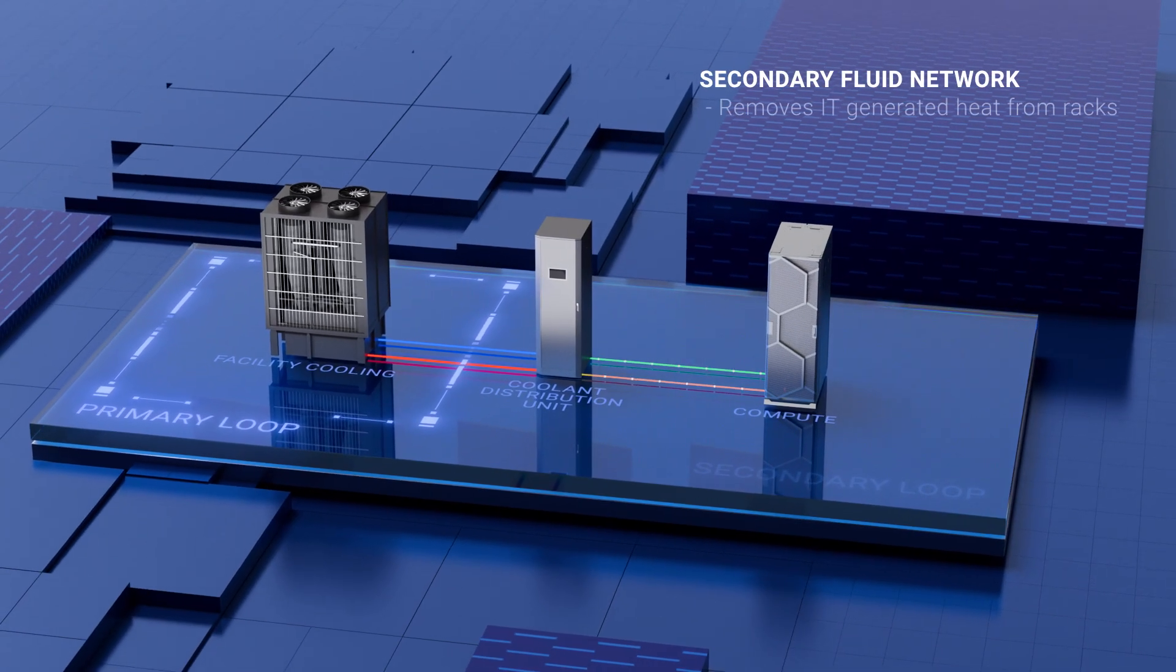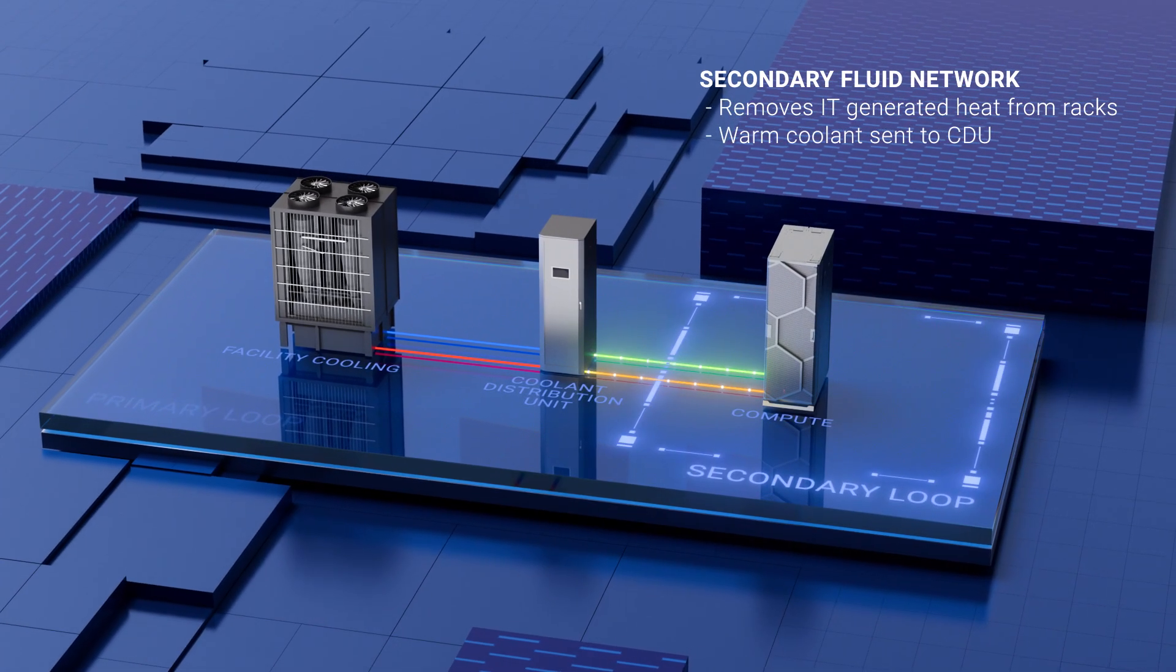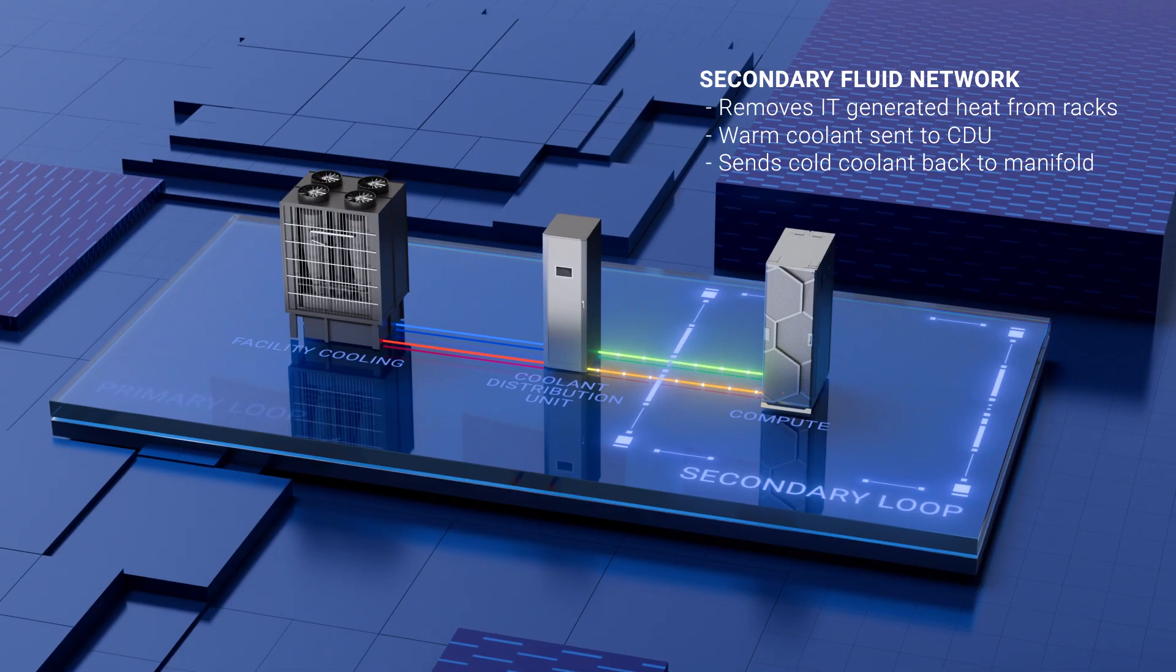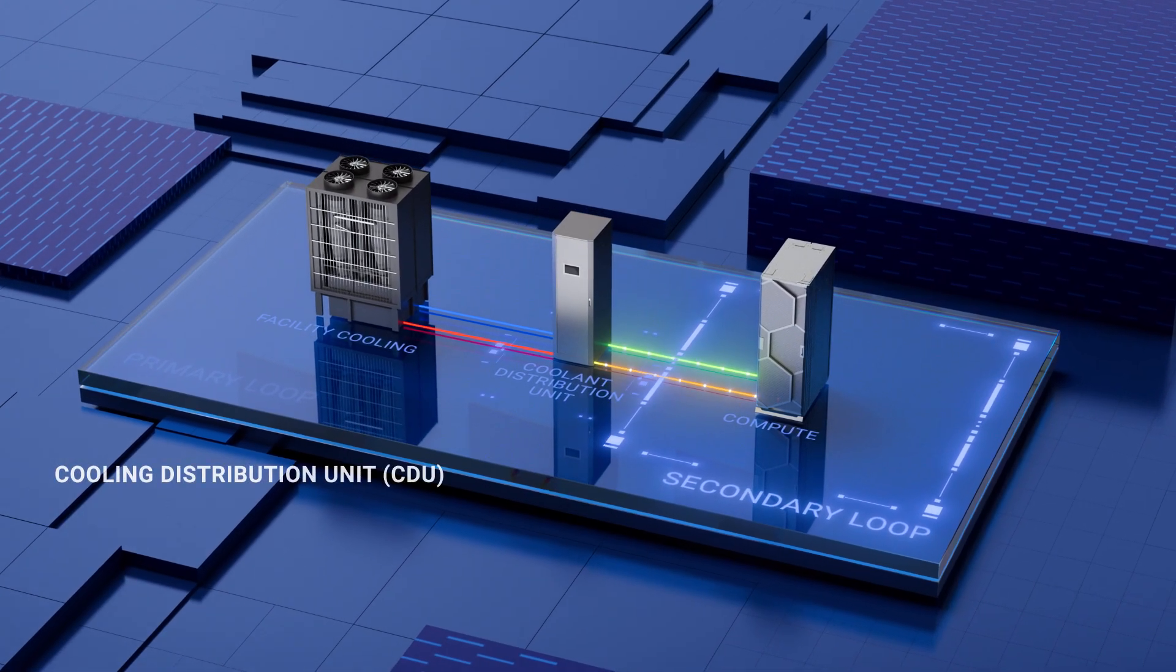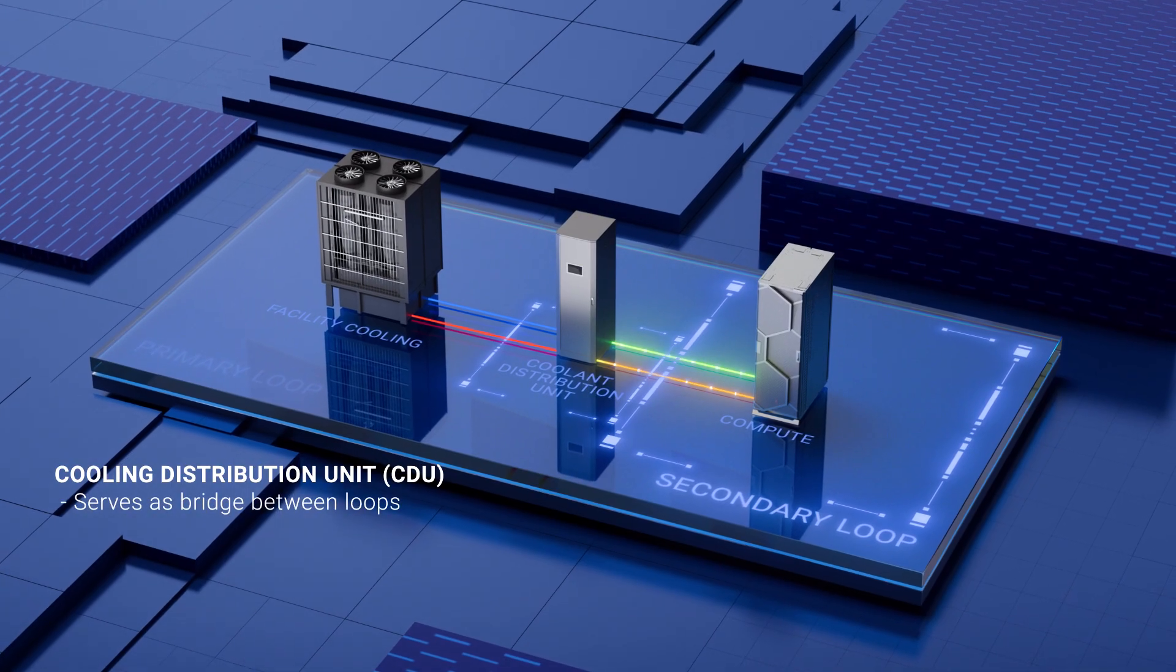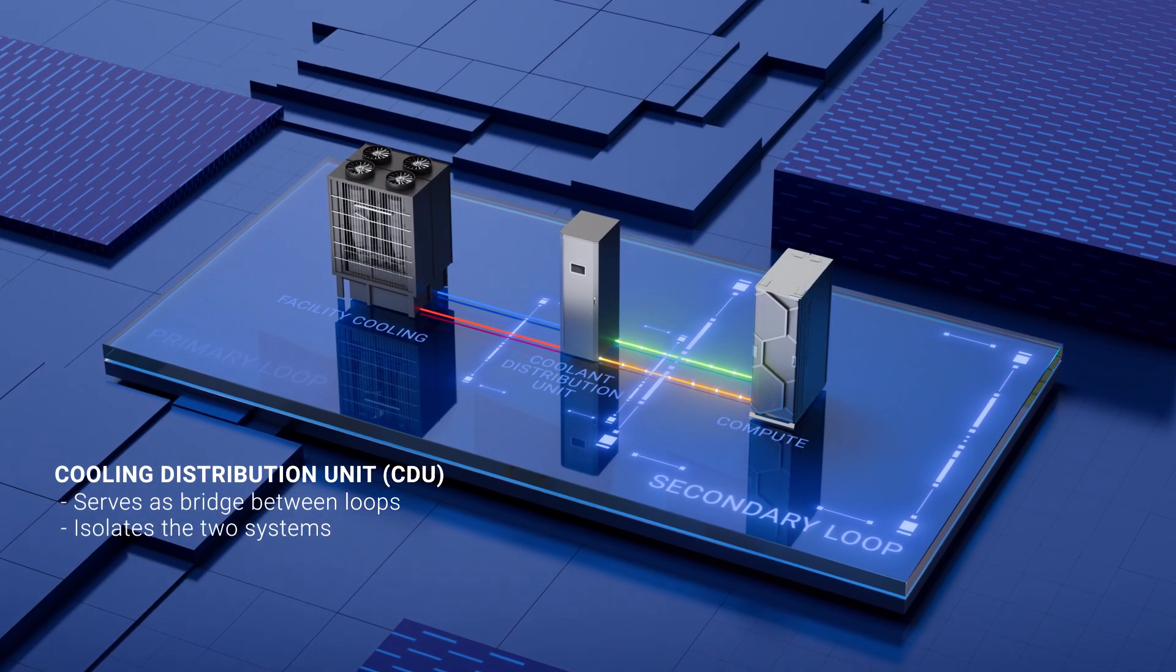The secondary fluid network refers to the circulation of coolant between the cooling distribution units, CDUs, and the CPU and GPU cold plates where most of the heat is generated. The CDU serves as the bridge between the loops and isolates the two systems for heat exchange.